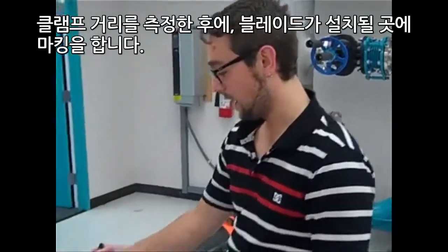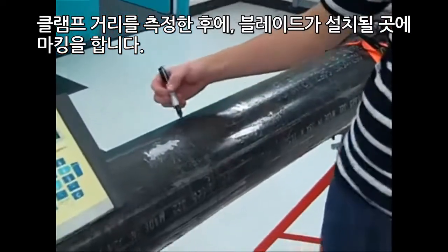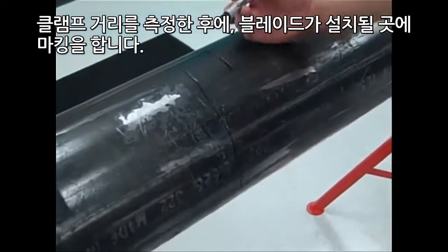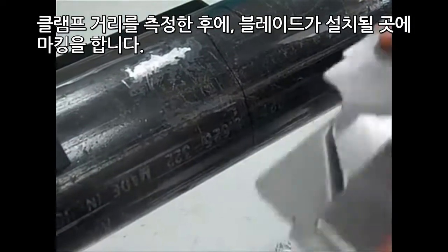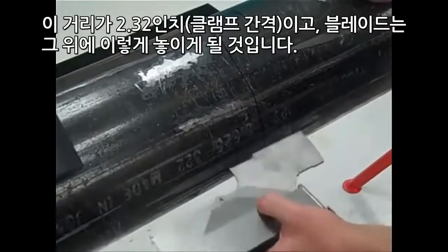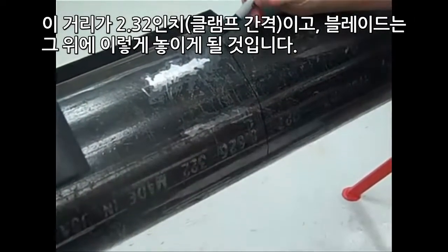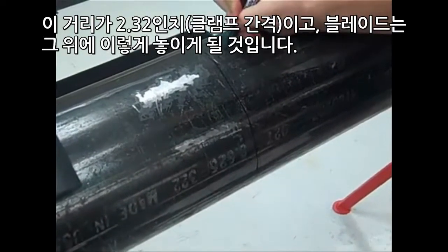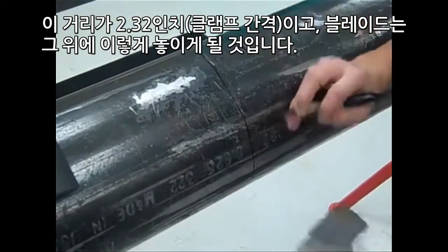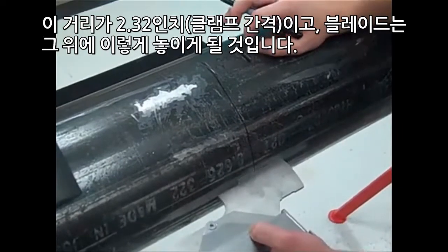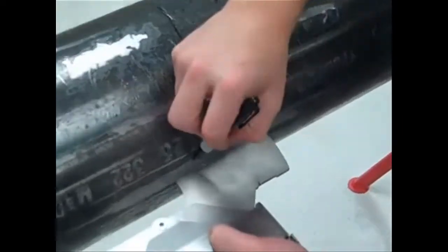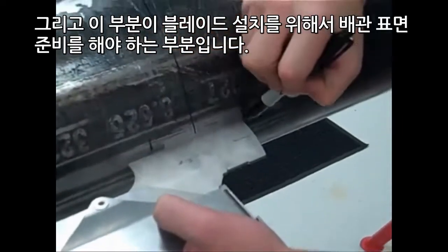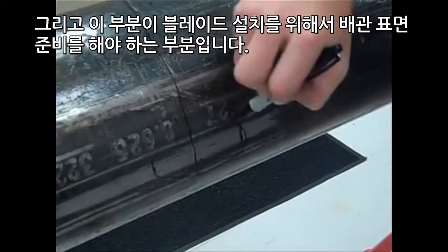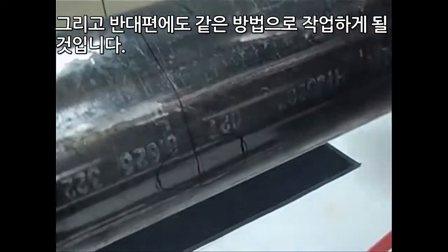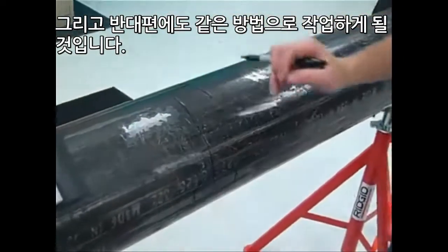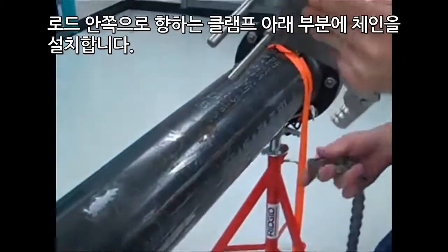Okay. After you measure the distance for your clamps, next you want to mark where your blades are going to be for your transducers. This is the 2.32 inches spacing right here. You want to put the blade right on top of it, and this is the area where you want to make your pipe preparation. And then do the same thing on the opposite side for a direct mount.